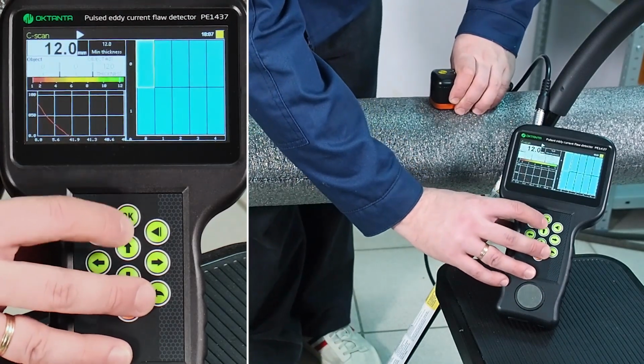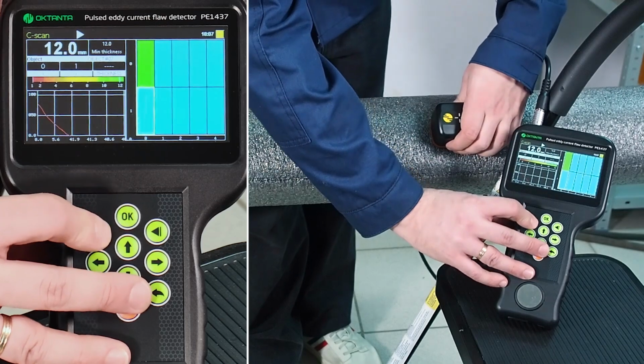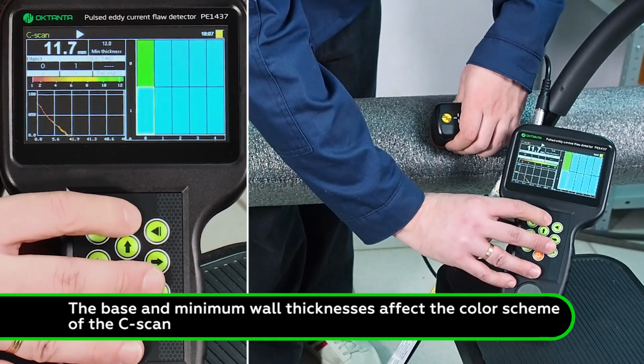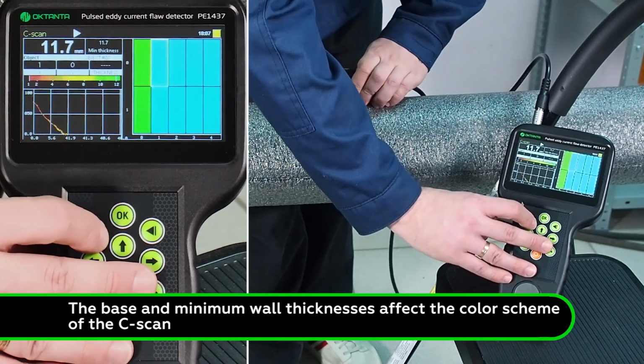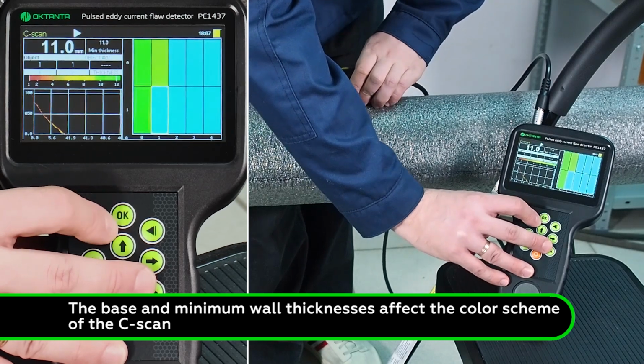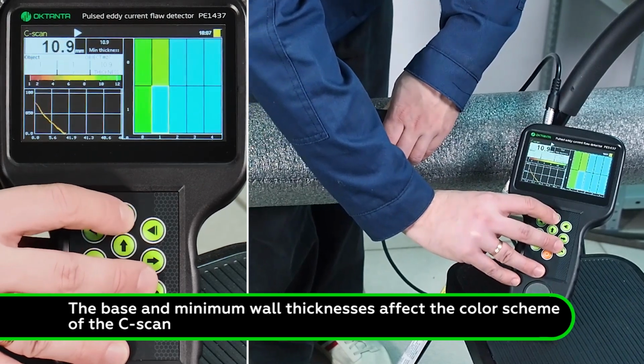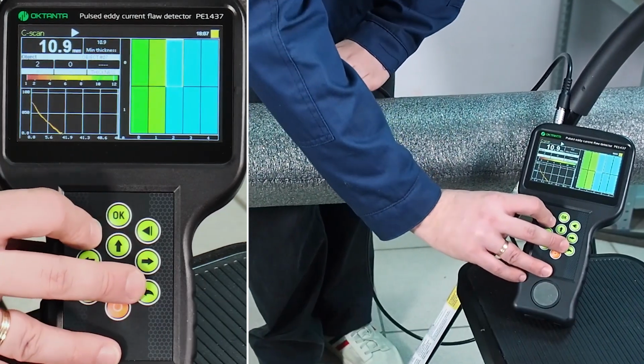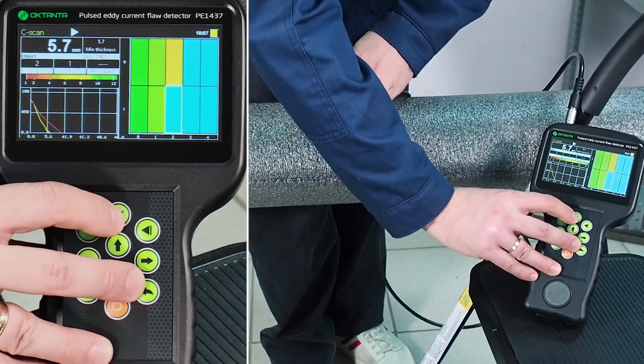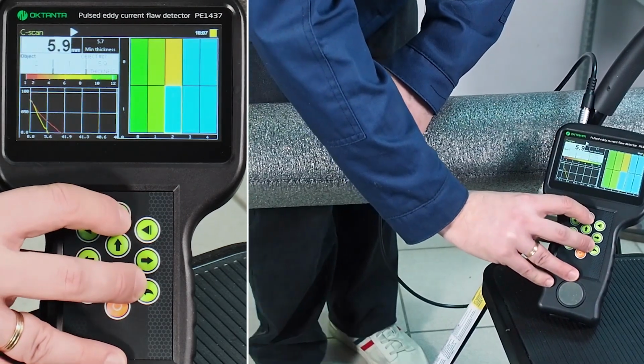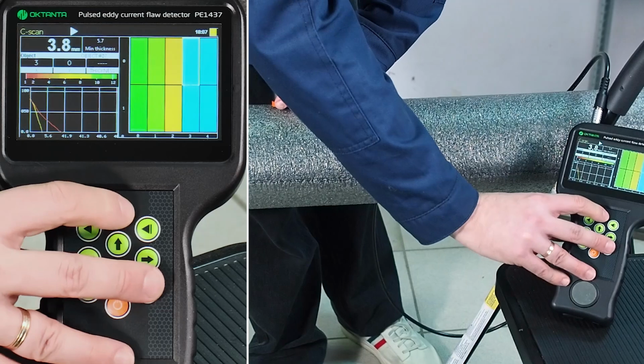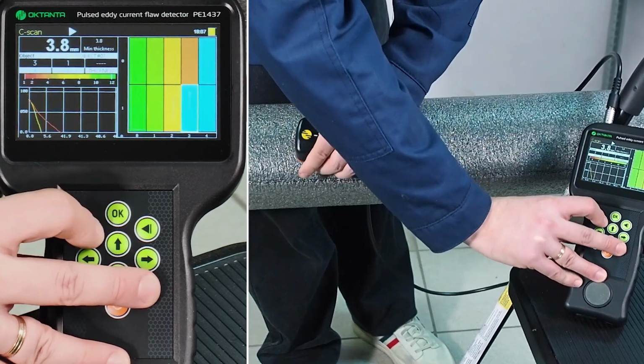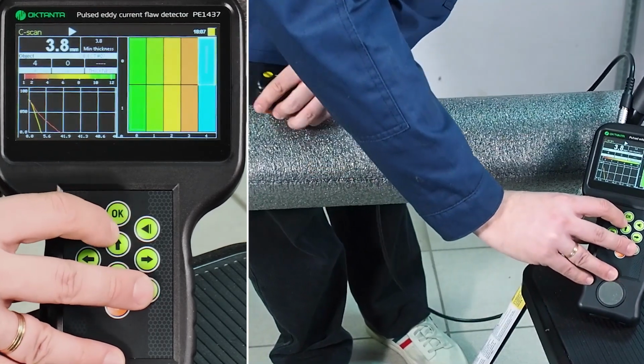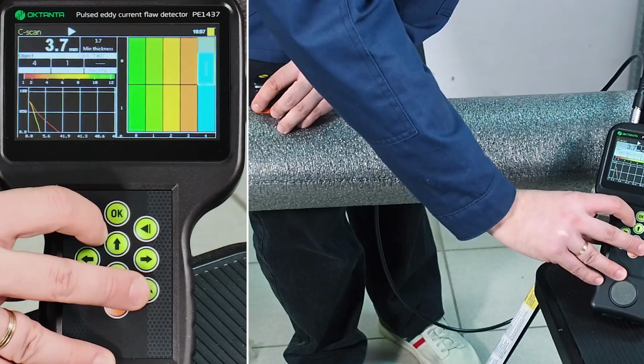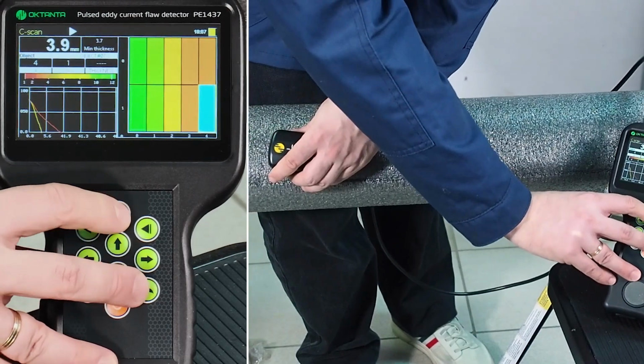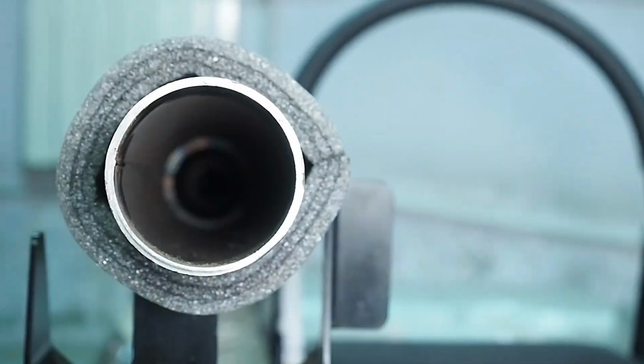Please note that the measurements with the pulsed eddy current flaw detector require a similar insulation thickness in the inspection area, with deviation of no more than 10% from the calibration point. In the area where the insulation thickness differs significantly, a new calibration is required. In addition, to eliminate interfering magnetic effects, the measurements must be taken maintaining the sensor direction relative to the pipe. We see a step transition of wall thickness from 12 millimeters to 4 millimeters on the C-scan, which corresponds to reality.